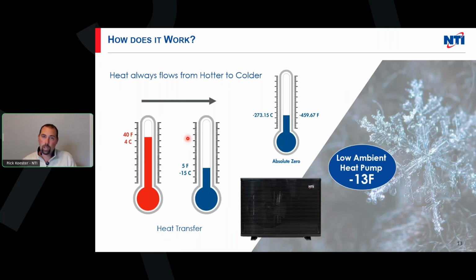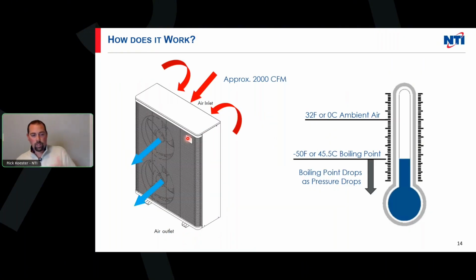We're talking about -13 as a low temp. If anybody asks how efficient it is at that temperature, we have some charts we can look at that will tell us. But for the most part, in single digits, down to zero, we're still really efficient with these machines. So we'll take a look at that. But this is kind of that difference in boiling point and ambient air. When you think about each one of these fans in a unit, now this is a 5-ton unit having 2 fans.